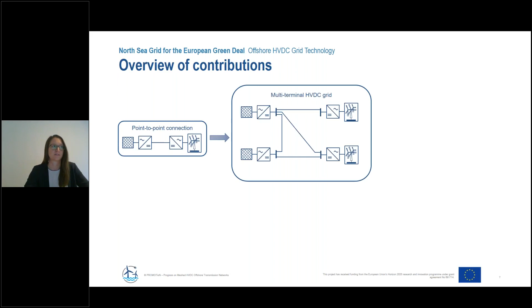We had a close look at DC protection systems, covering both the strategic side, so the strategies that could be used in future systems, the IEDs, but also new fault clearing equipment such as DC circuit breakers, which are needed for multi-terminal system protection.